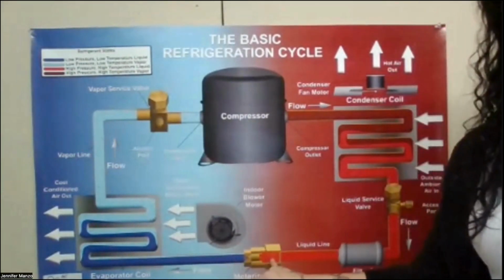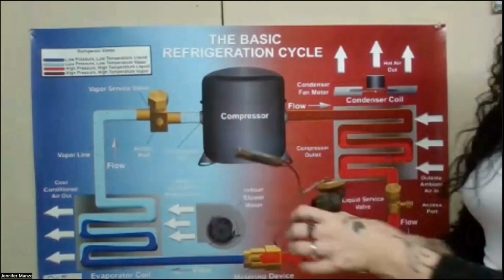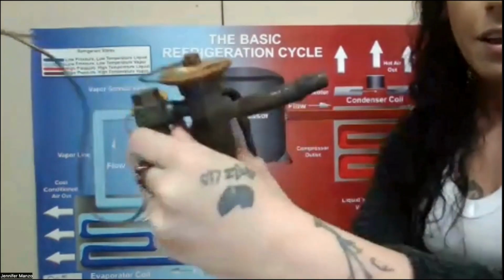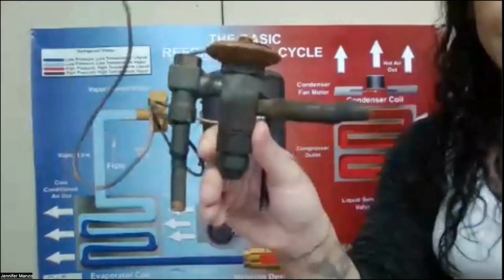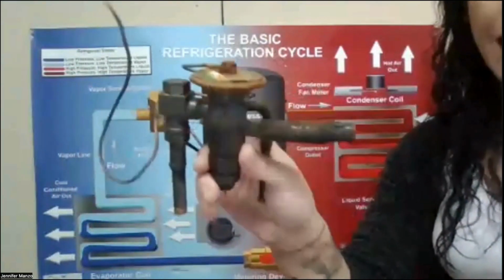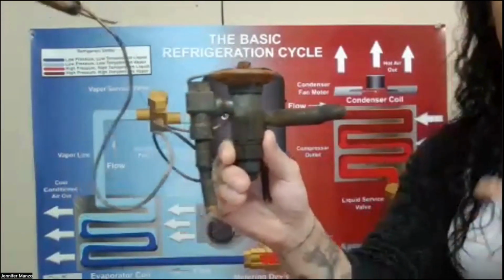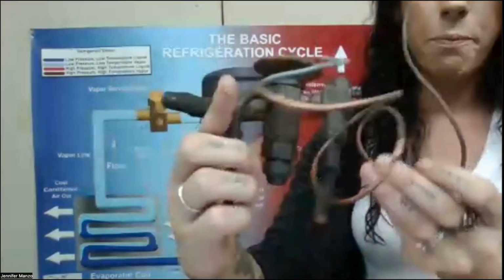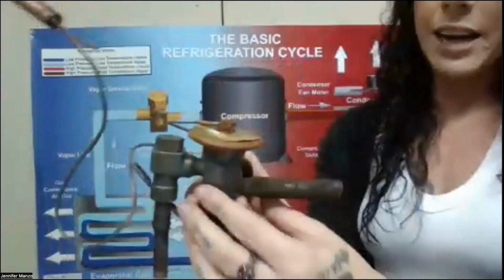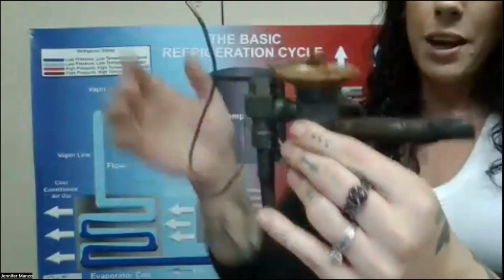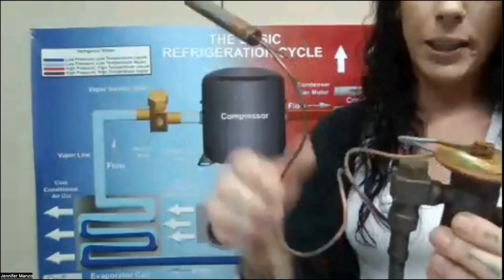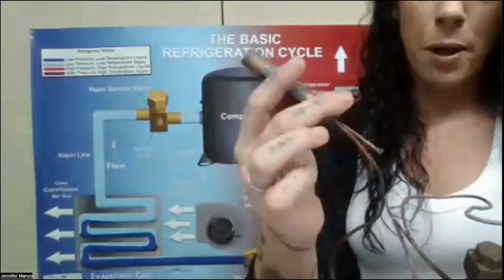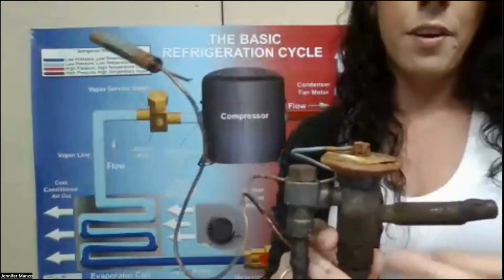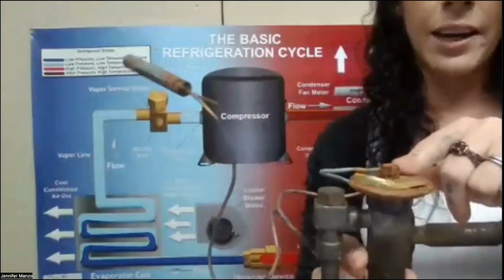And this is on a lot of the older systems and a lot of the smaller systems. But you will also see this. This is what you're used to seeing. This is a TXV, a thermostatic expansion valve. And this is what you guys saw in that refrigeration theory course. So this metering device has an inlet and an outlet here and here. It has a cap tube, a capillary tube. It has a sensing bulb, and then it has a valve, and it has a power head. So the power head controls the valve.